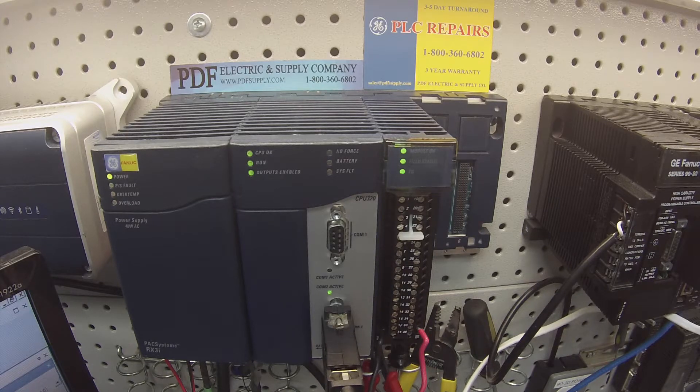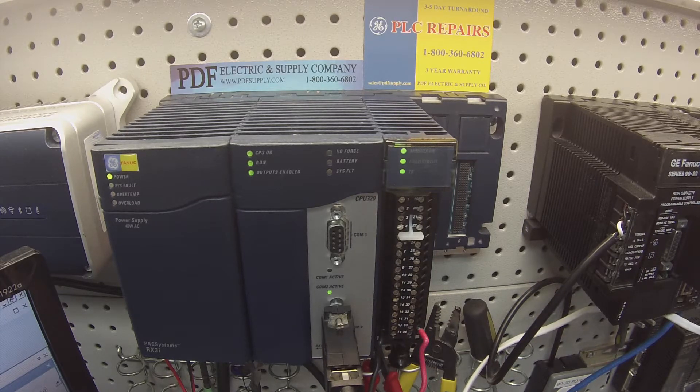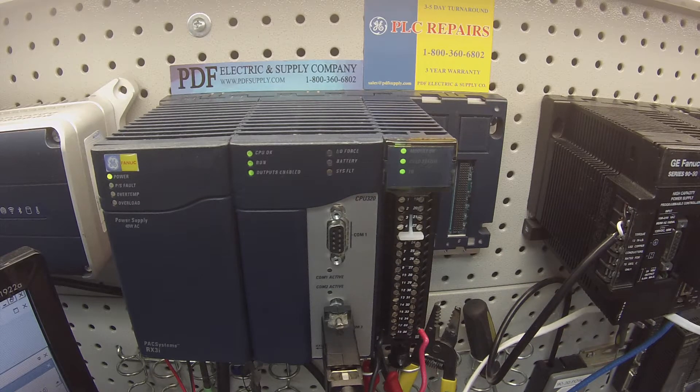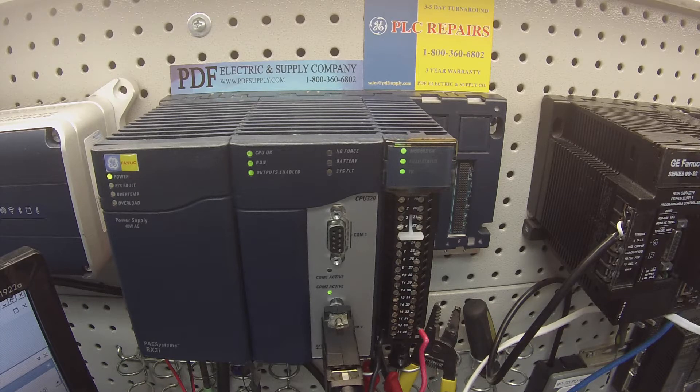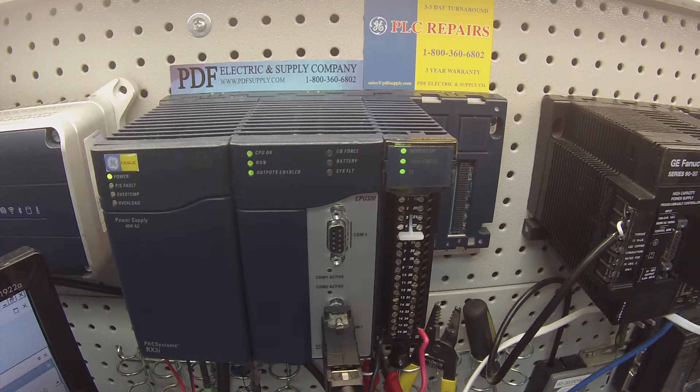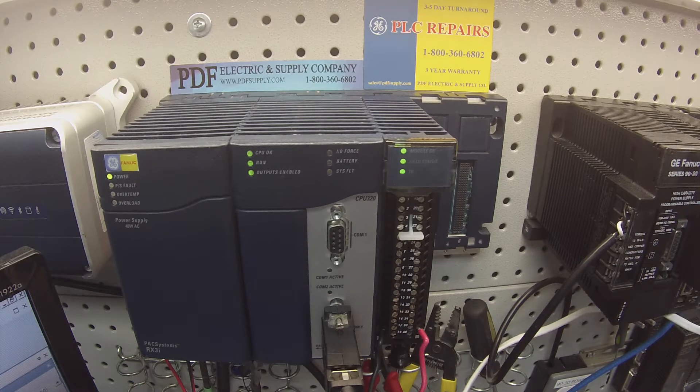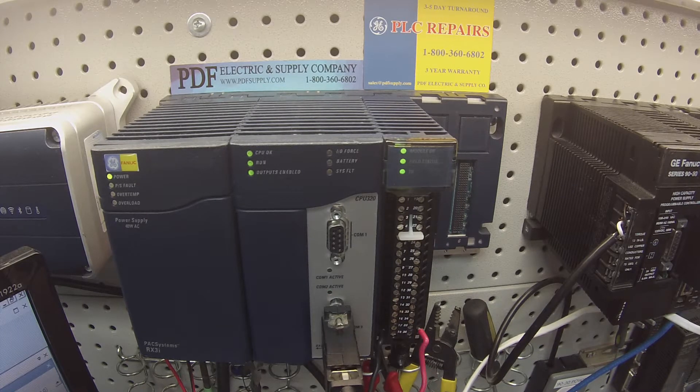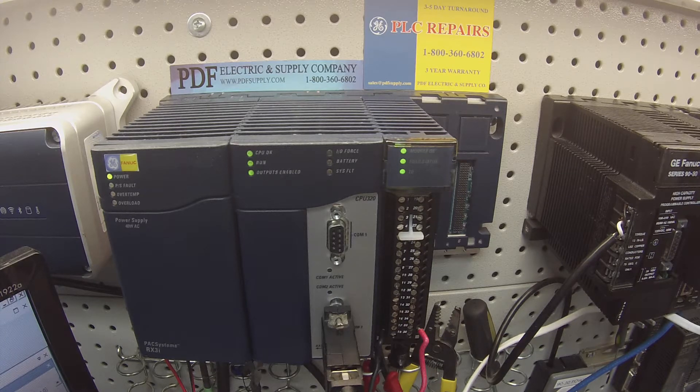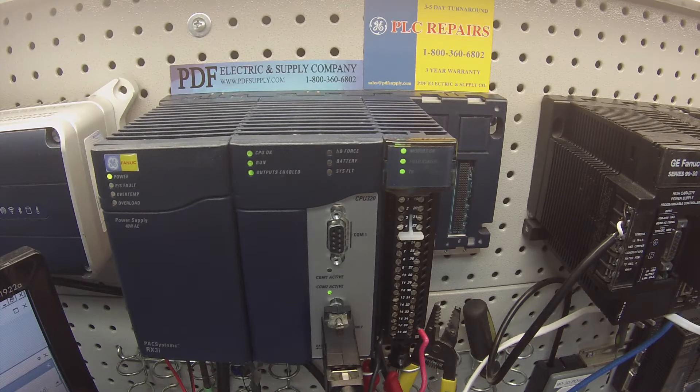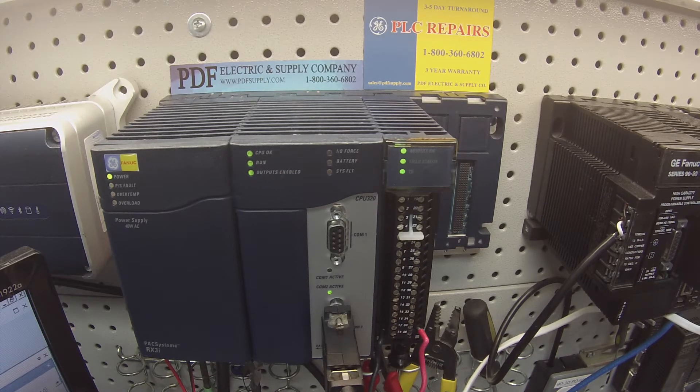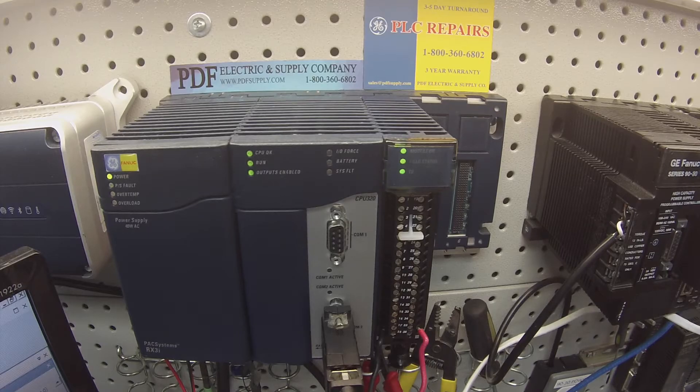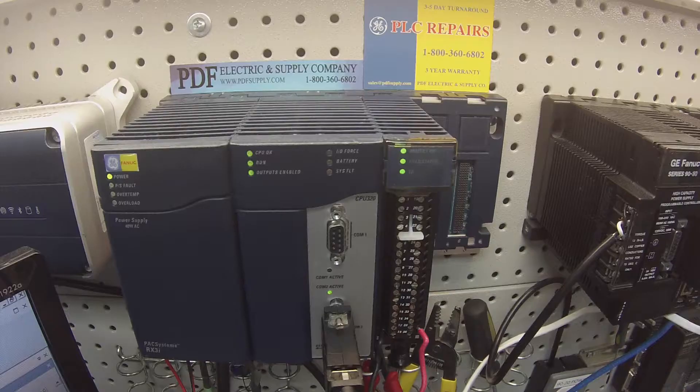So check for range and resolution. Make sure it can go up and down. Especially with milliamp, if you put in a value of 20,000 and you get 21 milliamps, that's great. It's a working circuit so far. If you put in half that value, it should cut in half. If it's stuck at full value, it's a failed card. It's a failed channel.